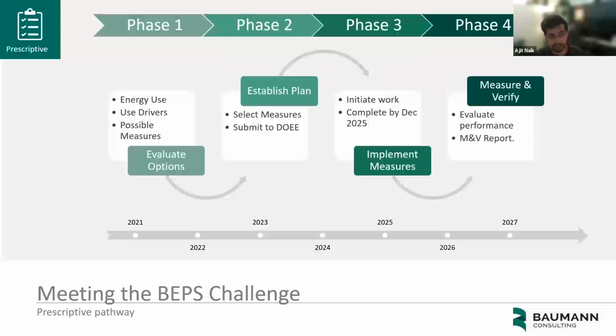Lastly, in relevance to retro commissioning is the prescriptive pathway. Basically, if your building doesn't comply with the BEPS standard during the first compliance cycle, you have the opportunity to implement a bunch of prescriptive measures from an a la carte menu of options. Each of these are designed to reduce your building's energy usage. There are a few stipulations that you have to follow for this compliance path. You have to have an energy assessment, sometimes called an energy audit, done by a qualified professional. You have to submit a package to DOEE for the set of measures that you want to implement. And you also have to submit for approval an operation and maintenance plan. So if you take this prescriptive route, there are some additional hoops you have to jump through, but one of the measures that you can apply is retro commissioning.